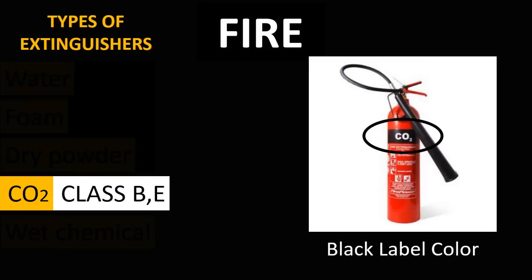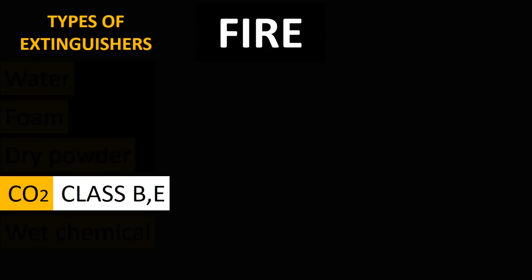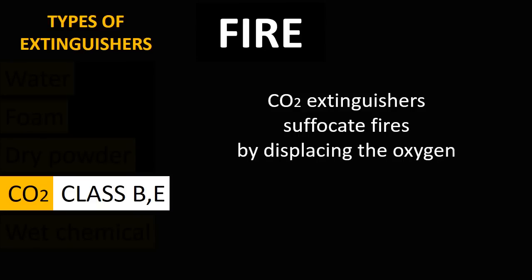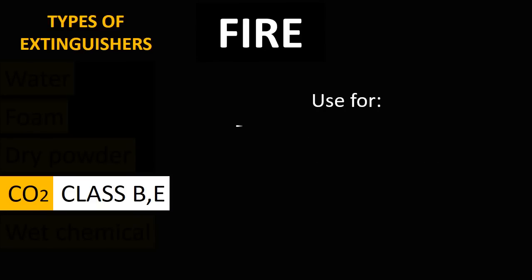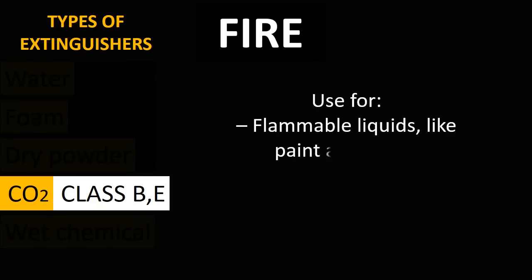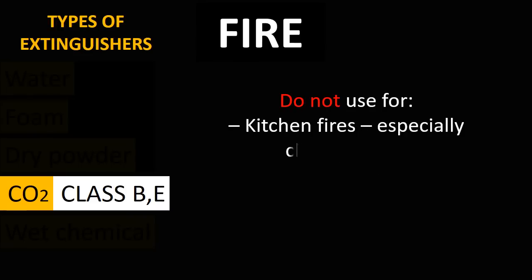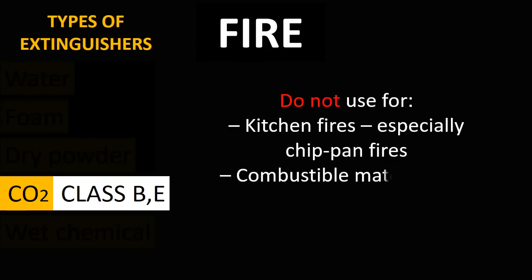Carbon dioxide fire extinguishers have a black label color. They suffocate fires by displacing the oxygen. They are used for flammable liquids like paint and petrol, and on electrical fires. Do not use carbon dioxide type fire extinguishers for kitchen fires, combustible materials, or flammable metals.